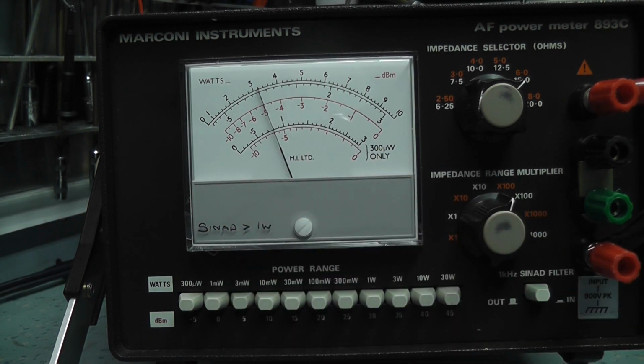Then, as long as you're feeding 1 kilohertz in, you press the Sinad button, and the level will drop back, probably about 10-12 dB. Basically the difference between the non-Sinad metered reading and the Sinad metered reading is your Sinad. It's not a straightforward readout - you can't just press Sinad and it will give you the Sinad. It doesn't work like that. Basically it's an early form of Sinad meter, and although it does work, it won't give you a live reading of your Sinad all the time. You'll have to work it out from the unfiltered response and the filtered response, and take one from the other, and that will give you the Sinad meter reading.